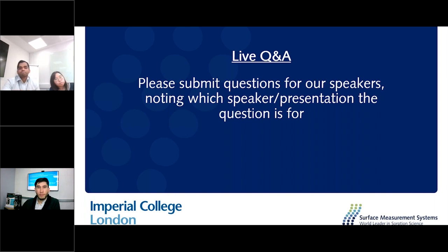All right, thank you. Question for Paul from Jan Steckel. They ask, what is the type of detector that is used in the BTA instrument? There are a number of detectors available in the breakthrough analyzer. There's of course the capability of coupling it with a mass spec, but the design philosophy behind our particular brand of breakthrough analysis was that it would be equipped with individual detectors that allow you to do 80% of the experiments that you might want to do.